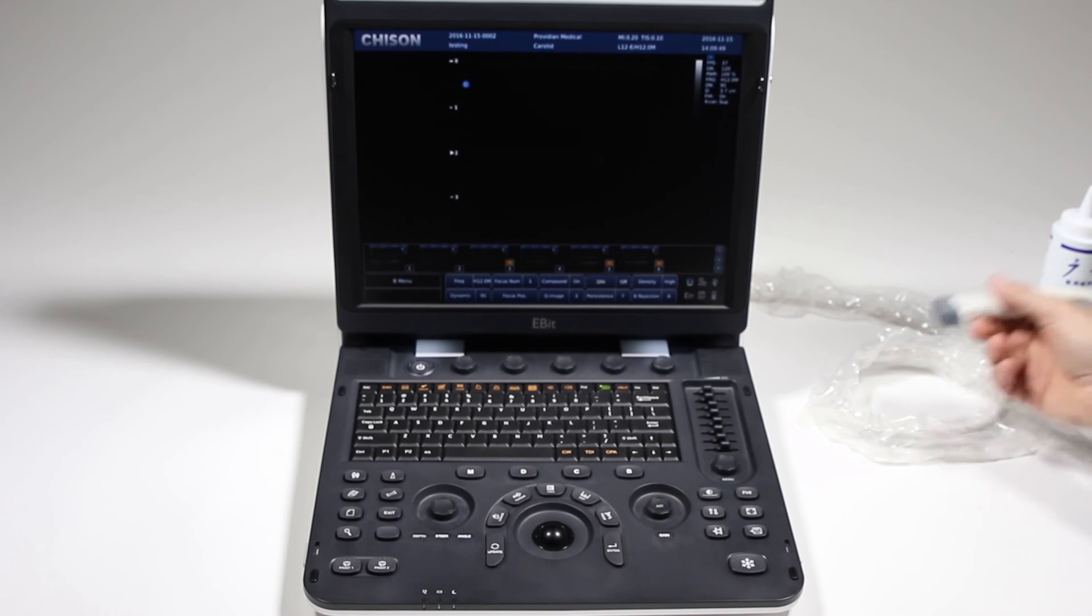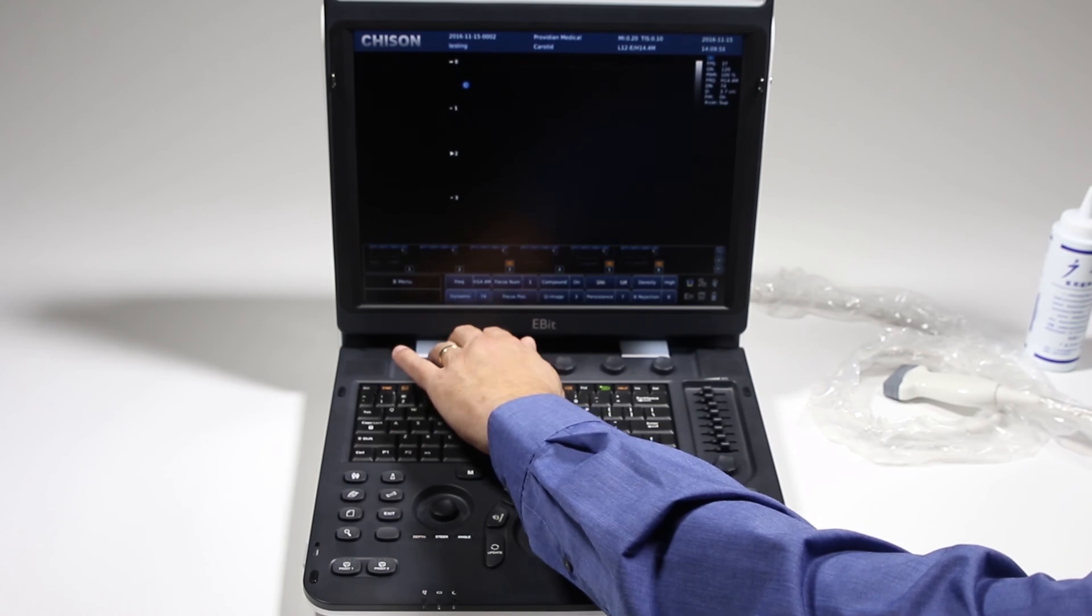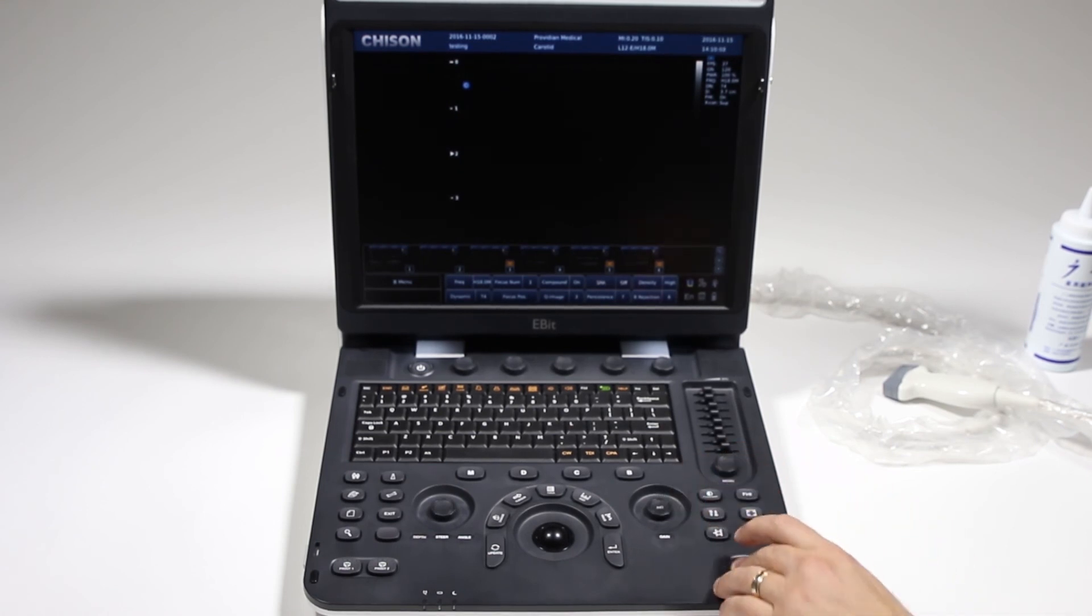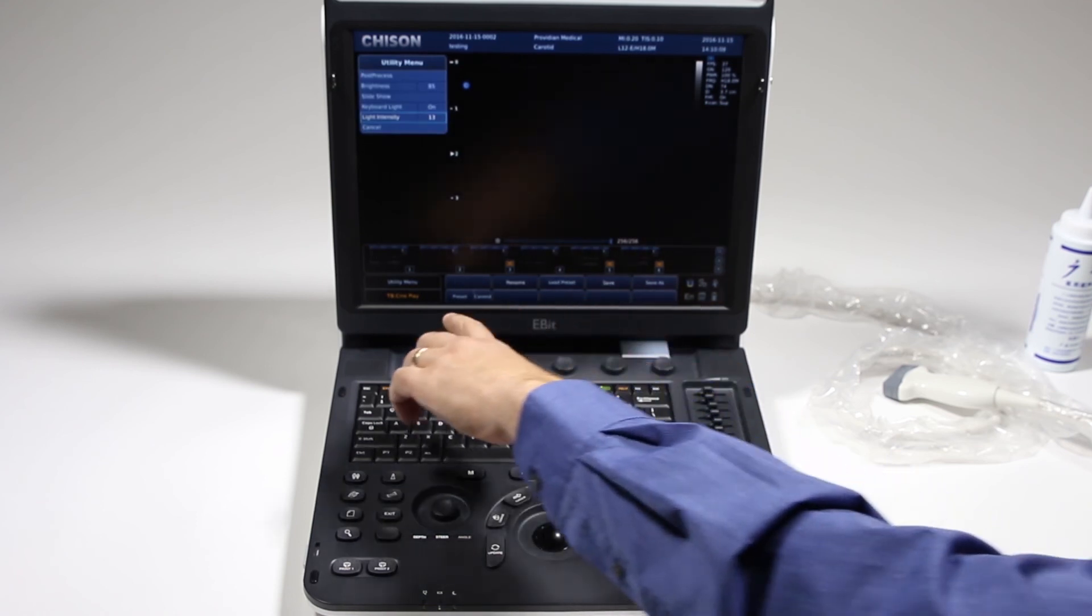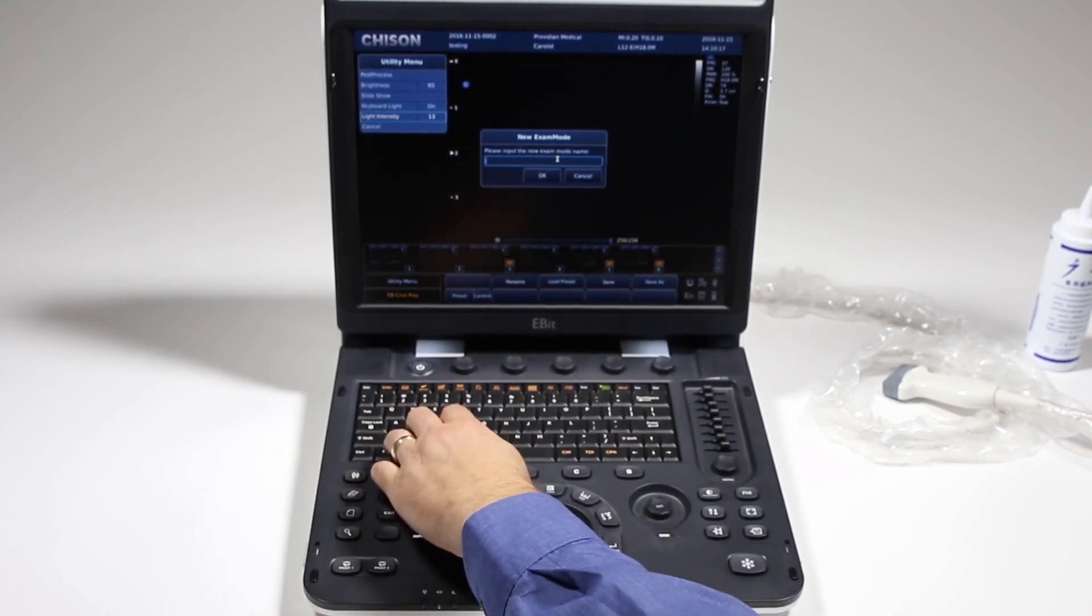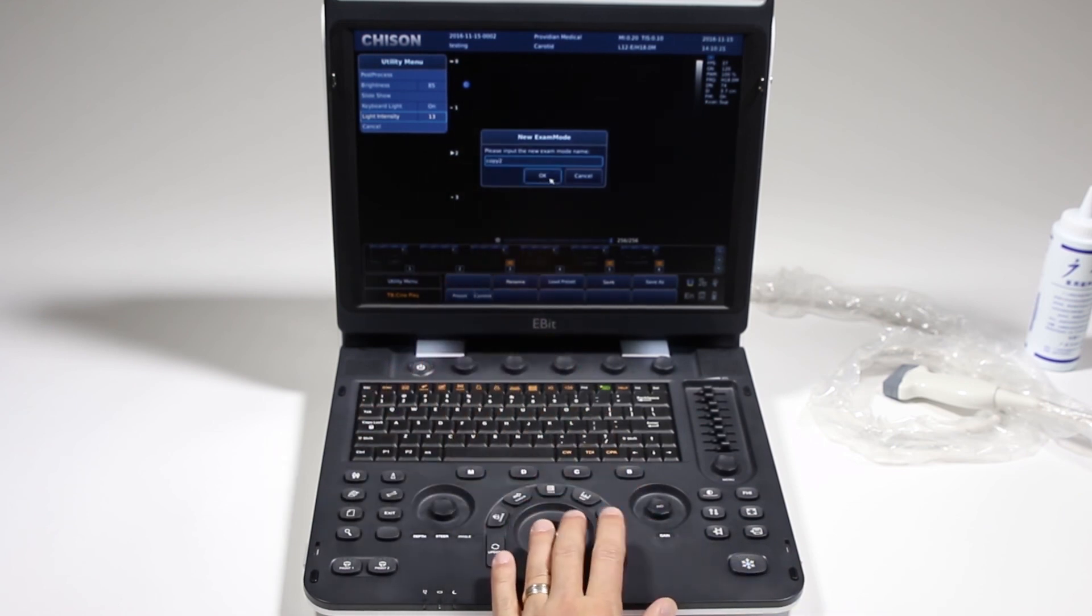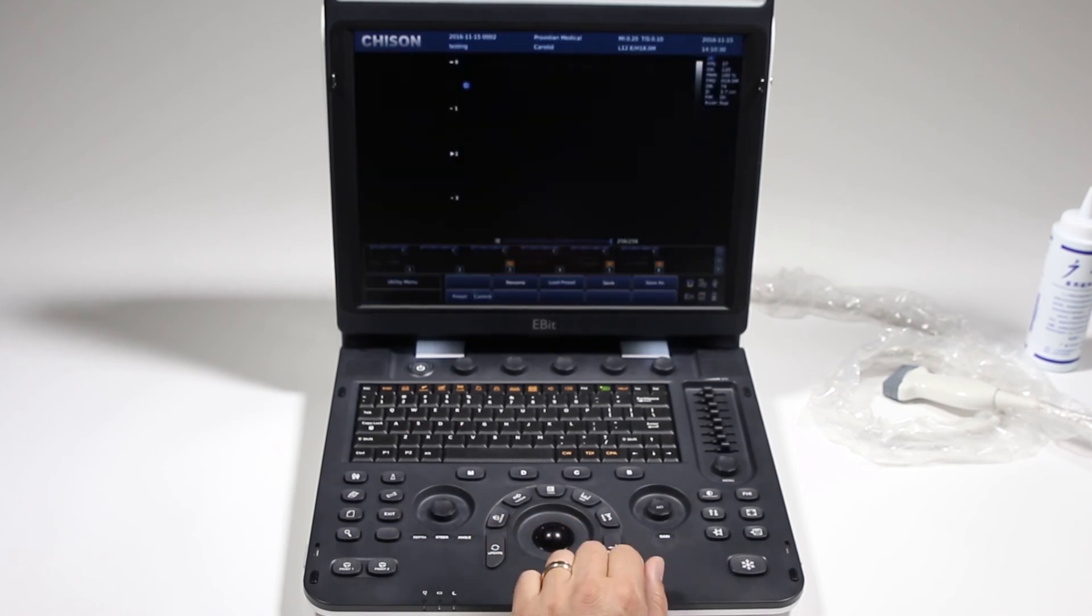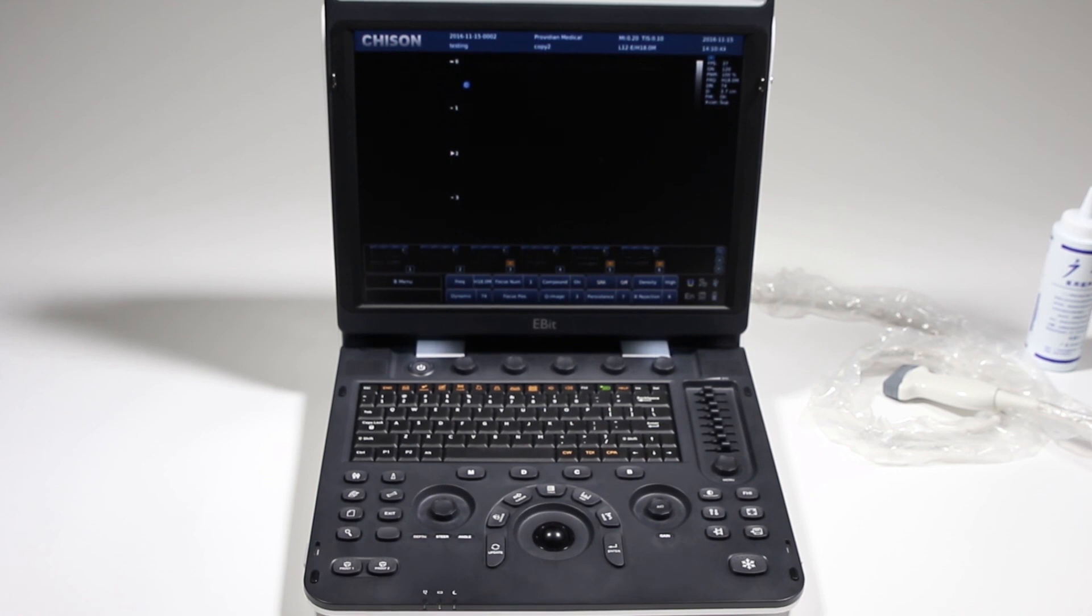If you want to save a custom preset, let's say we made those changes, the persistence, and we wanted a different frequency and dynamic range where we optimized our image and we're really happy with it. Say I want it to go to 18 megahertz each time. I showed we can press freeze, press menu and it goes to that utility screen. I'm going to hit utility and here I can save by clicking save as and it says copy of carotid. I can type in my own name. I'll just type in copy to and I'll click OK. And it's saved. So now when I go to this probe screen, I can scroll down and my new preset is right there. I can click on that and it's automatically going to save every change I made. So that is now a default and I don't have to keep going back and making new changes to it and really optimize my workflow.